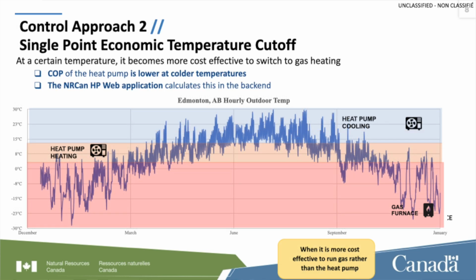The other one is a single point economic temperature cutoff. The COP of the heat pump is lower at colder temperatures. That's the coefficient of performance. Electric resistance heat has a COP of 1. It's 100% efficient. As we get colder, the heat pump itself will work, but your COP is below 1. So we want to cut it off when it's economical, and it's more economical at a higher temperature where it has COPs of 2 and some in the 3s.